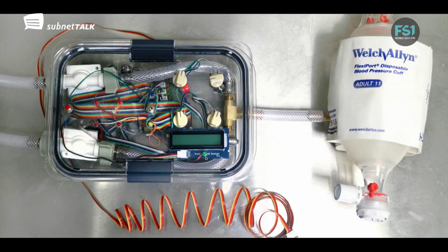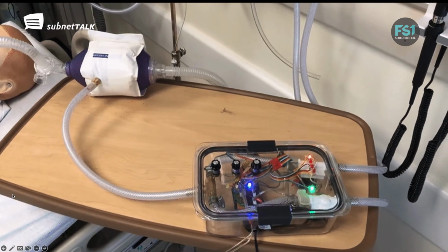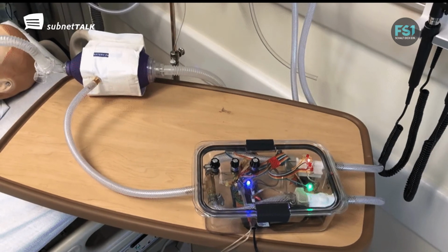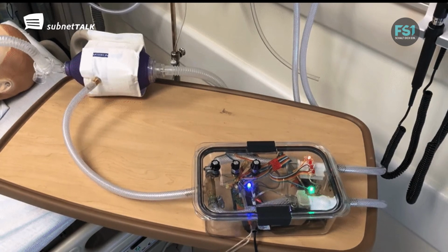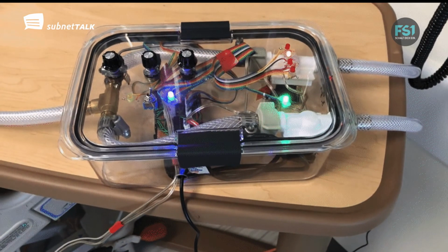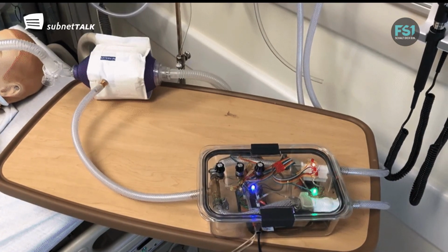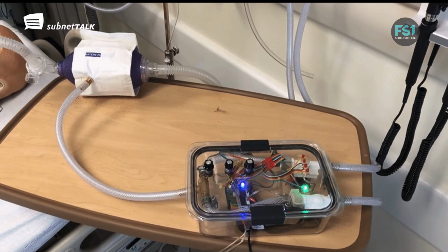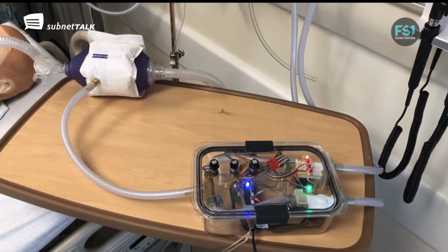By using common equipment from the hospital, we took a blood pressure cuff, the cuff that inflates and makes pressure on your arm to measure your blood pressure, and then just used some PVC valves and an Arduino. We thought everybody would have this around. Then we inflate it with the air and vacuum of the room. All hospital rooms have air and vacuum because they need to vacuum things, and also they need air for ventilators. So we actuated this, and we can make 400 milliliters of tidal volume at 30 breaths per minute, and 800 at, I can't remember exactly, but we essentially hit all the benchmarks that you need for proper ventilation.